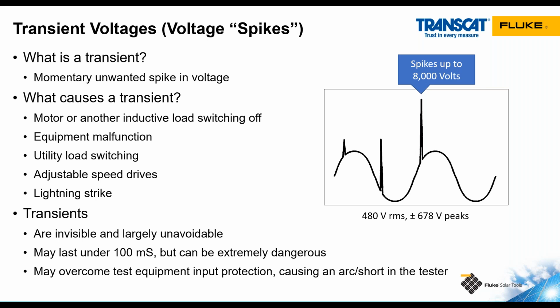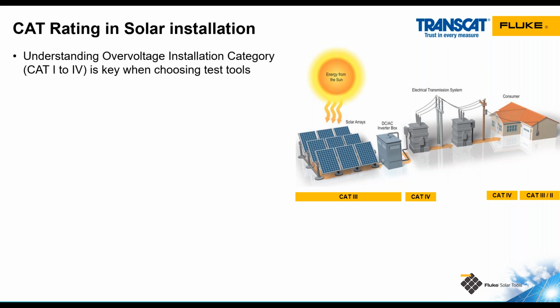And what happens is if you're testing voltage when a transient voltage spike occurs, if your tool is not properly rated, it may overwhelm the tool. It may damage the tool. It could cause a safety hazard to the technician using the tool. So we need to make sure that the tool is designed to withstand these transient voltage spikes without causing a potential safety issue to the technician. Now we do this through category ratings. There are 4 categories of electrical equipment, 1 through 4. The higher the category rating, the more potential there is for larger transient voltage spikes.